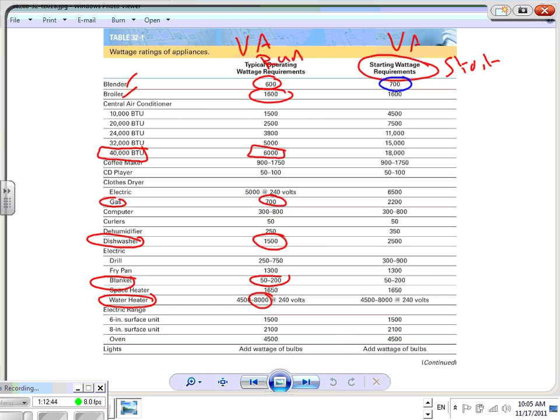Take this. I have a broiler. It takes 16. There's nothing on that one. Look, this is substantial. For 40,000 BTU air conditioning, it will take 6 kVA to run it, but it will take 18 kVA to start the compressor. 3 times more, and that's coming from motors. 3 to 6 times more is coming from motors.